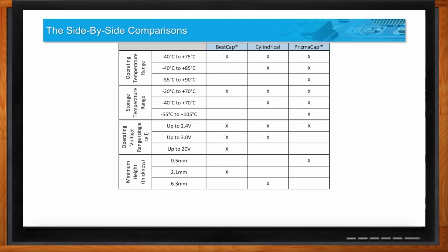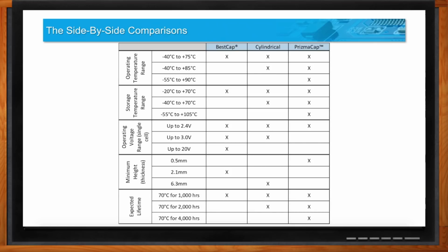All right, Shawn, let's talk about a really important part of all of this, expected lifetime. We touched a little bit on this. The lifetime expectations on the BestCap, our qual data is 1,000 hours at 70 degrees C. We have field operation data where we show that it's been in the field for 10 years at 55 degrees C constant in gas meter, underground meter type systems. The parts are very, very stable there. It's 70 degrees C, 1,000 hours, which is literally less than 3 months, guys. So we've got to understand that lifetime, as we cross over that 55 degrees C, becomes shorter and shorter and shorter very, very quickly.